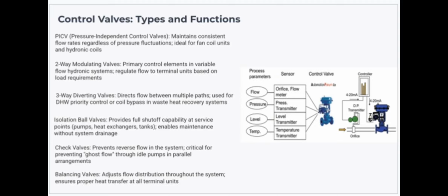Three-way diverting valves direct flow between multiple paths, used for DHW, priority control, or coil bypass in waste heat recovery systems. Isolation ball valves provide full shutoff capability at service points, pumps, heat exchangers, tanks, etc. They enable maintenance without system drainage, which is good in case something bad happens. You can save the money without having to drain it all and then redo it again. Check valves prevent reverse flow in the system, critical for preventing ghost flow through idle pumps in parallel arrangements.